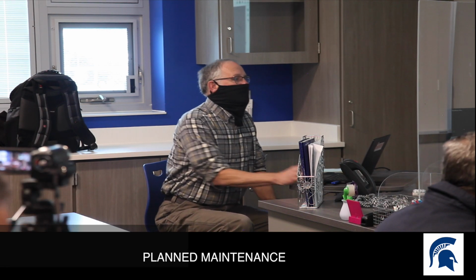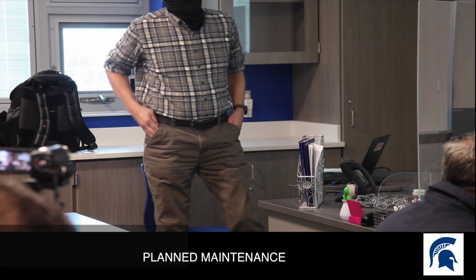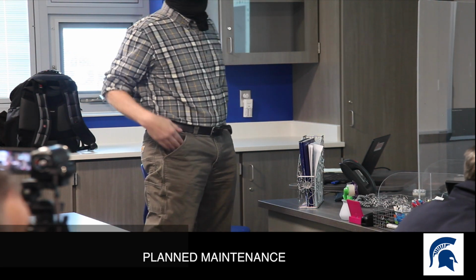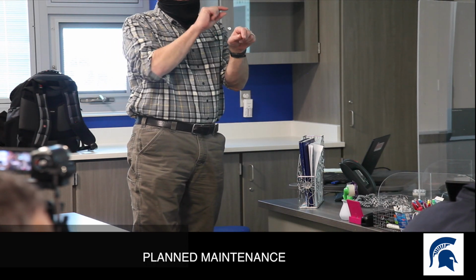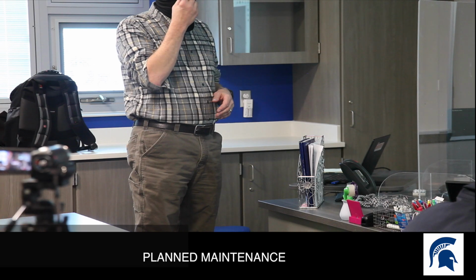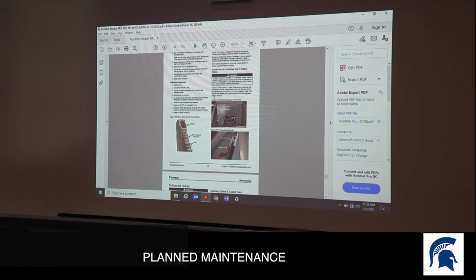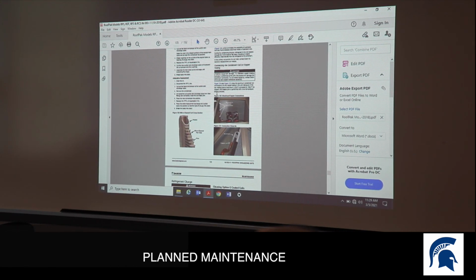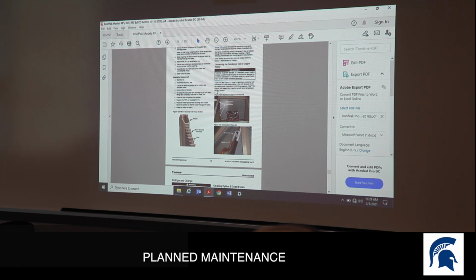So here's the condenser coil. These are called micro-channel coils. If you've ever seen condensing coils on a residential unit, they're just a coil with tubes running through them — they are no more. Almost every manufacturer has moved to micro-channel. You can see in that diagram, it's like a car radiator: very little space between, very high heat transfer. Because of that, they don't hold refrigerant. The older condenser coils, you could overcharge and the refrigerant would back up. There's so little ability to hold refrigerant now, it just fills up, and you need to go off head pressure because there's no place for the refrigerant to go.